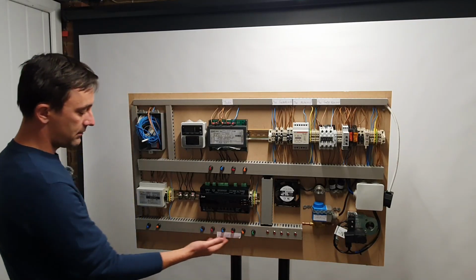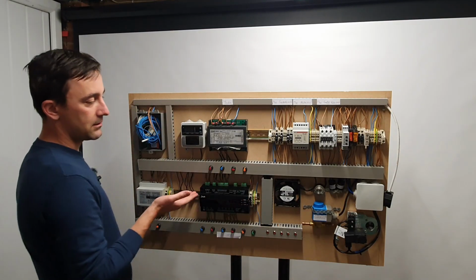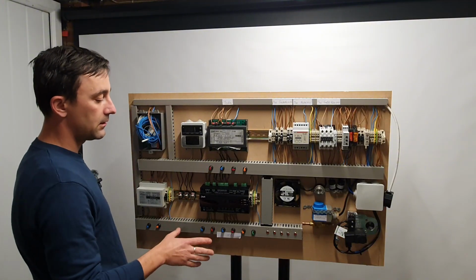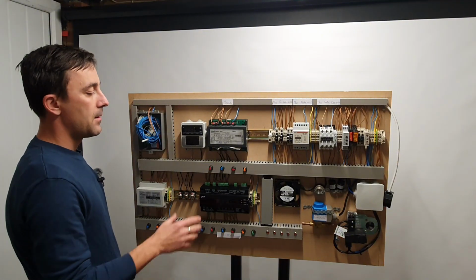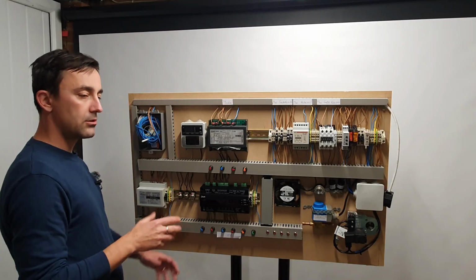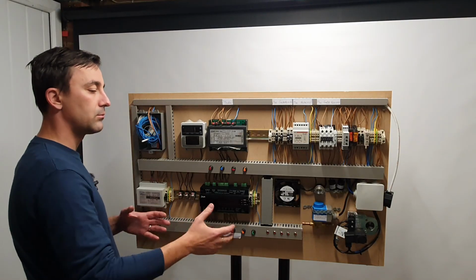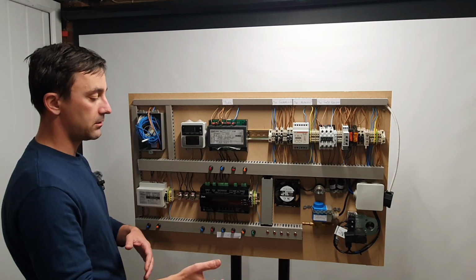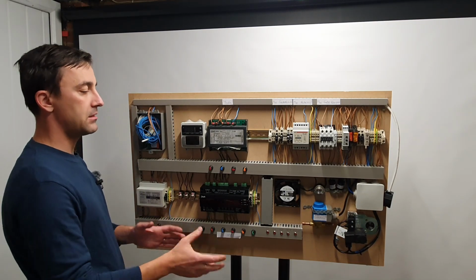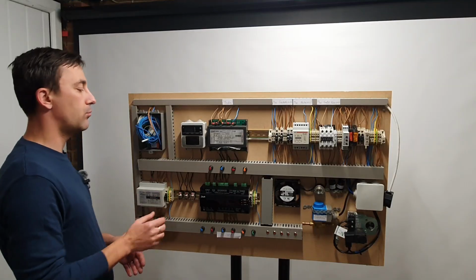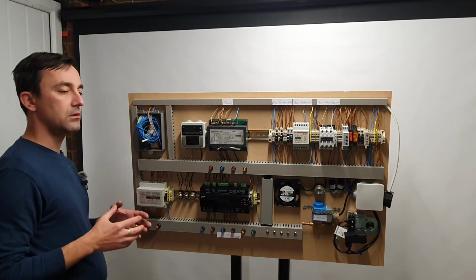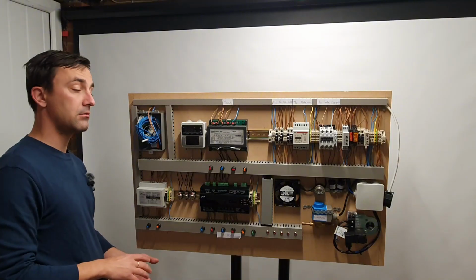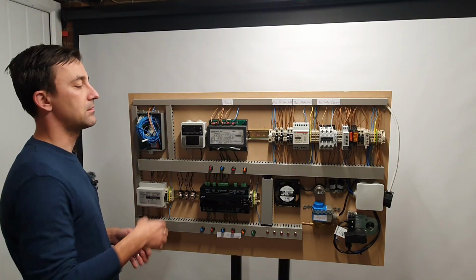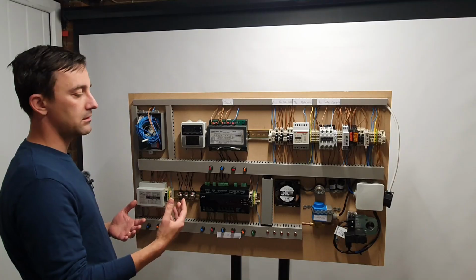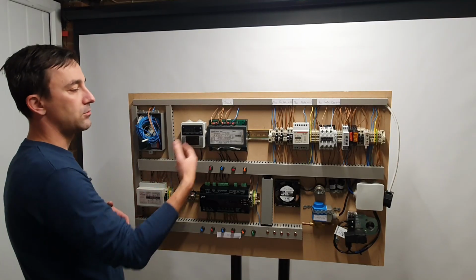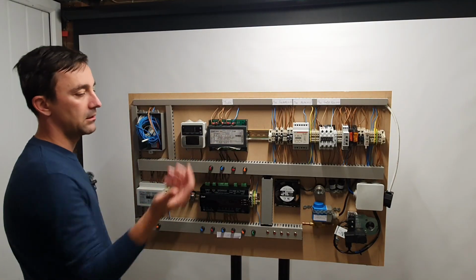Obviously, we've got these potentiometers. So I decided to use potentiometers because I want to be able to change the temperature in order to simulate certain situations. On a basic principle, it kind of works the same way a probe would work, because a probe with a temperature increase or decrease will change the resistance, and that change of resistance is fed to the controller, and that's how we get our temperature display.